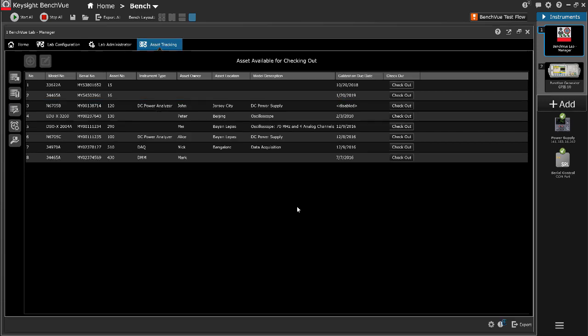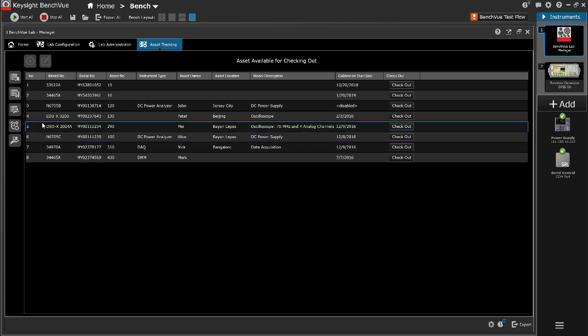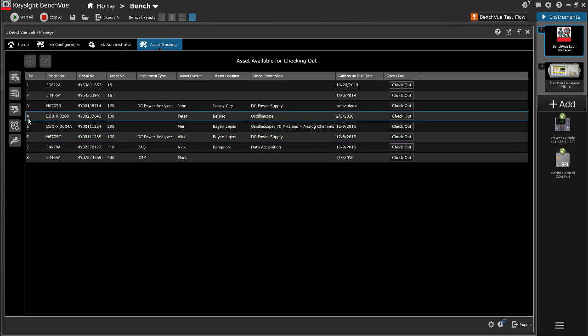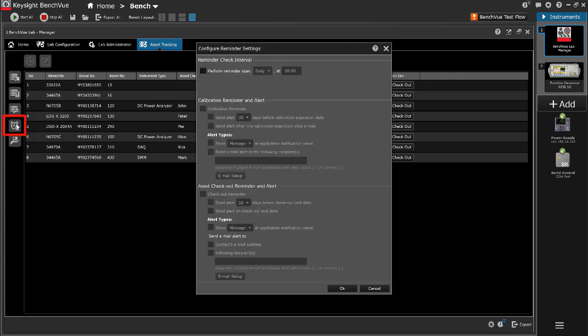The BenchVue Lab Manager provides automatic reminder notification for instrument calibration due date and asset checkout end date. The reminder notification settings are customizable according to the user preferences. To configure reminder settings, click on the configure reminder settings icon.